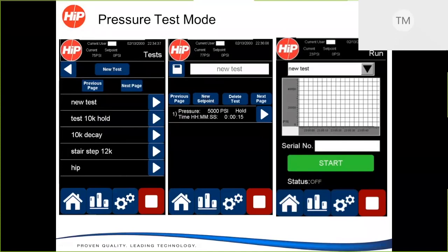So let's say hypothetically you want to drive to 5,000 psi, as we show here. That would be one set point. We'd drive the pump up to 5,000 psi, and then we would do something, maybe a hold test, a decay test, something like that. If we wanted to follow that automatically and run up to, let's say, 10,000 psi, for example, we'd hit new set point, and it would give us another opportunity to enter one of these values.